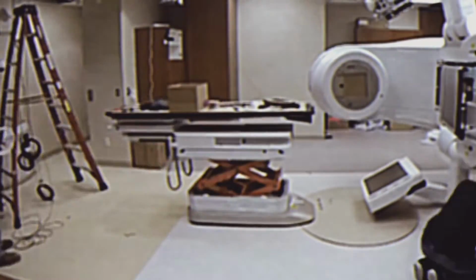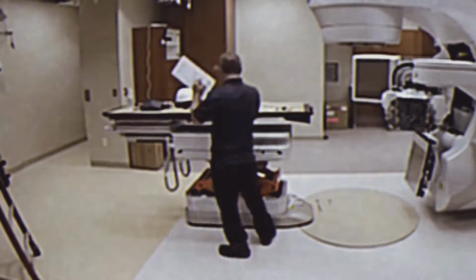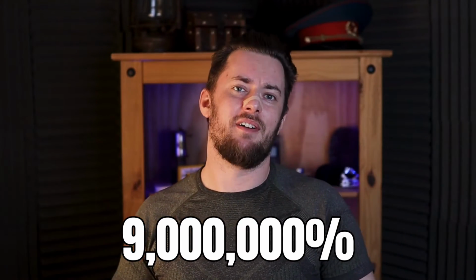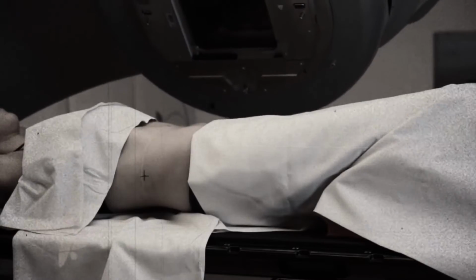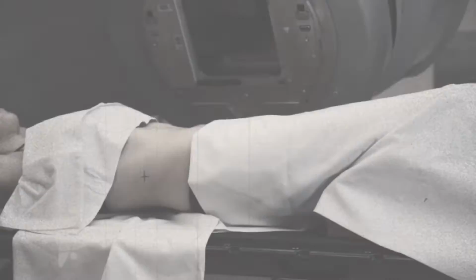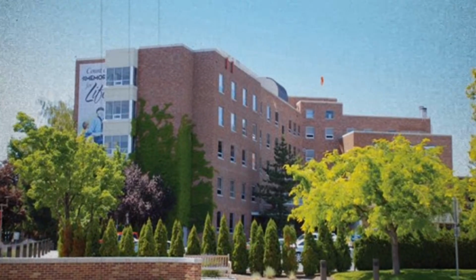AECL dispatched engineers to examine the Therac-25 unit. They introduced a software modification, and later claimed that the machine was now 9,000,000% safer. A month later, in December of 1985, a third woman was burned by a Therac-25 installed in Yakima, Washington — the exact machine AECL claimed was 9,000,000% safer.